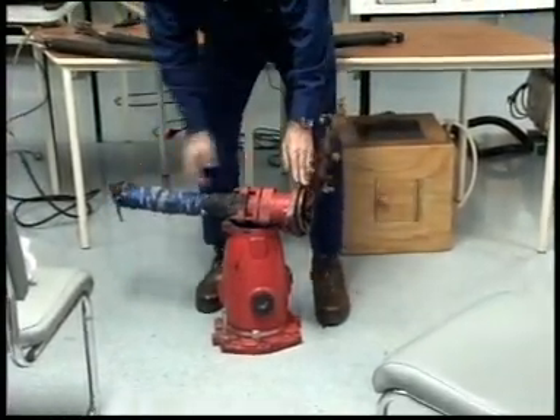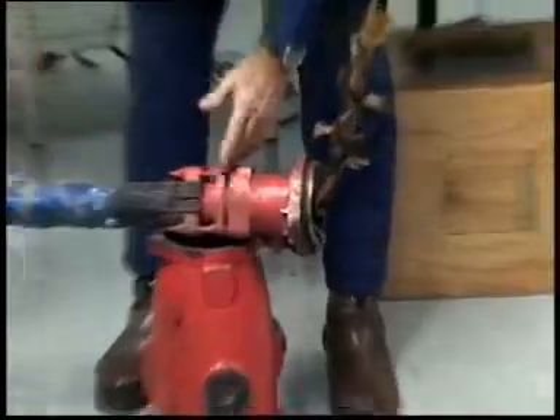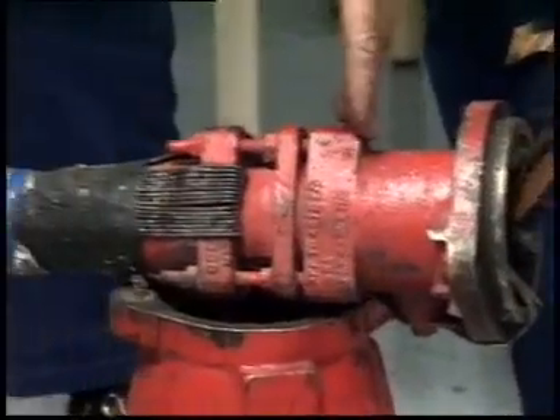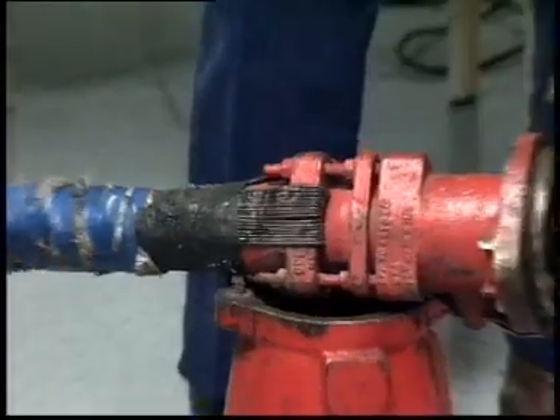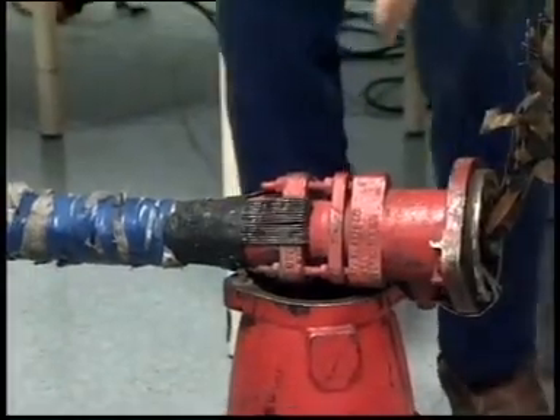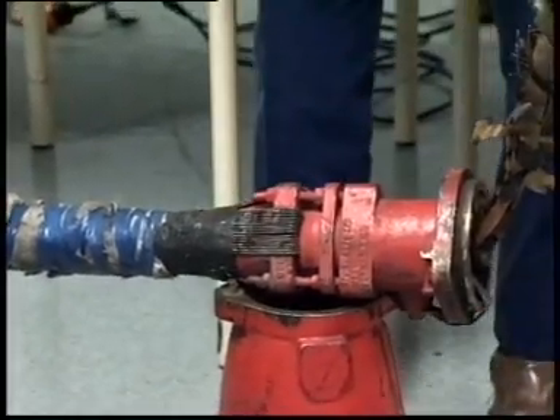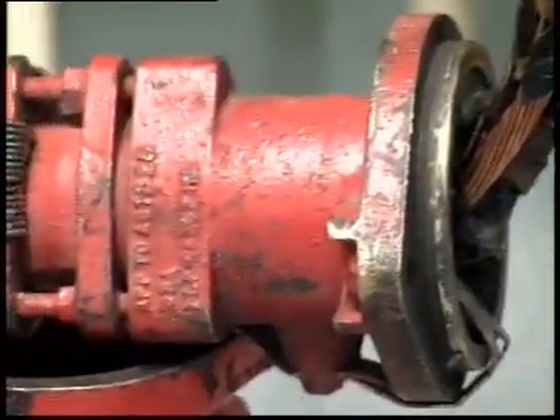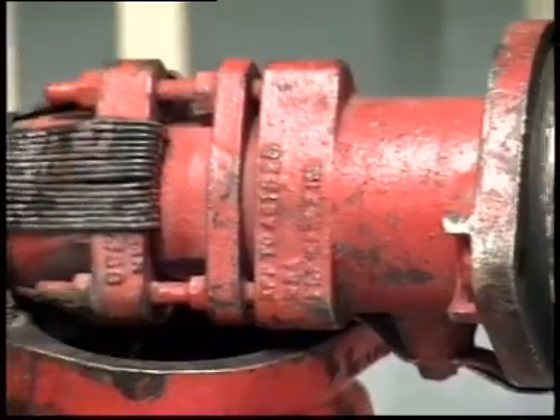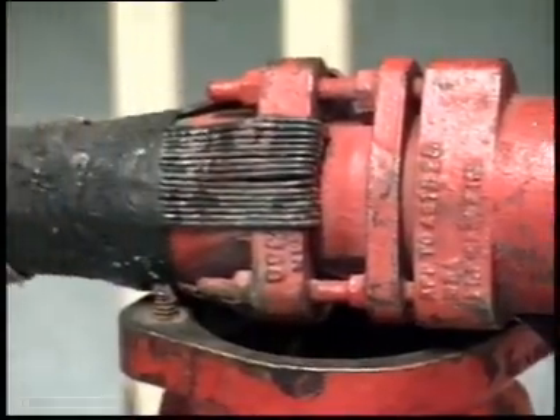Now these are very heavy, these things, and where the damage occurs is usually within that section there, because the plug end isn't handled very well. You should have a minimum radius at the back end of about 1.5 metres, I would suggest. That's where the damage occurs, and that's where you start damaging the lead and the papers. If you bend it too sharply, the papers inside will crack open. And if they crack open, you've got a good chance of having a face-to-face fault.